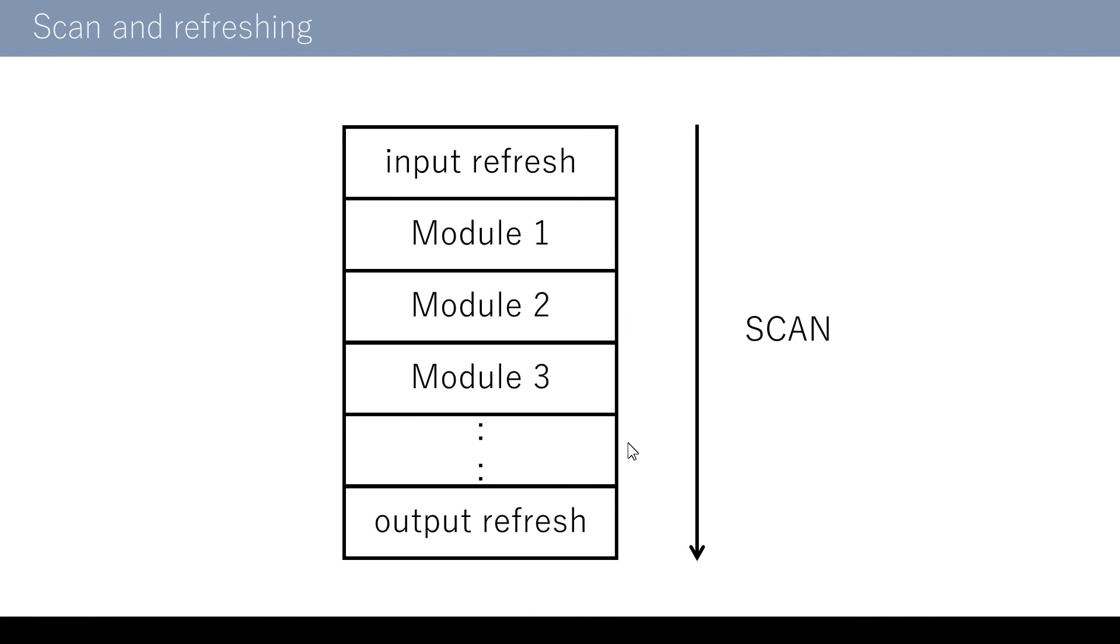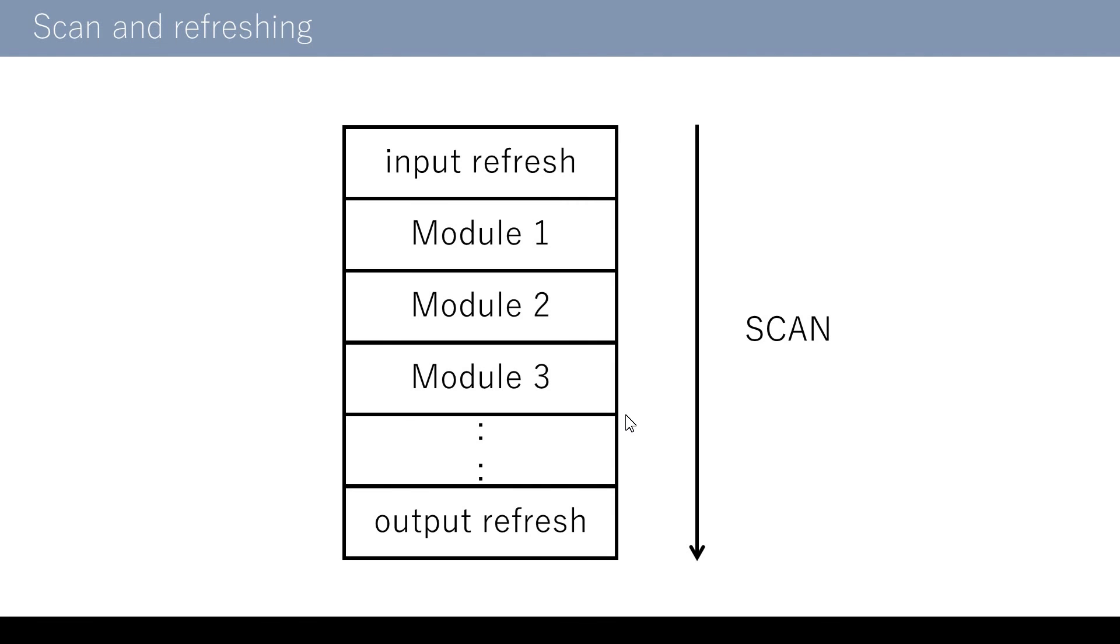On-off status of input-output data allocated to the expansion unit is reflected before and after execution of the module. Before execution of the first module, the input side data are loaded from each unit. Then, the program is executed in a descending order. After execution of the last module, the output side data are delivered to each unit. This series of operations is called a scan. The KV series executes a program by repeatedly executing the scan process.